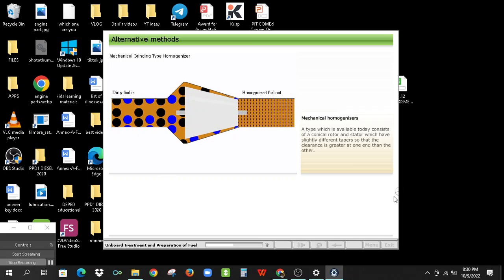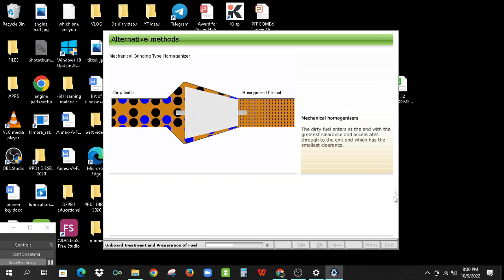A type which is available today consists of a conical rotor and stator which have slightly different tapers, so that the clearance is greater at one end than the other. The dirty fuel enters at the end with the greatest clearance, and accelerates through to the exit end, which has the smallest clearance. You may come across homogenizers fitted in the system on board some of your vessels, usually working alongside centrifuges.